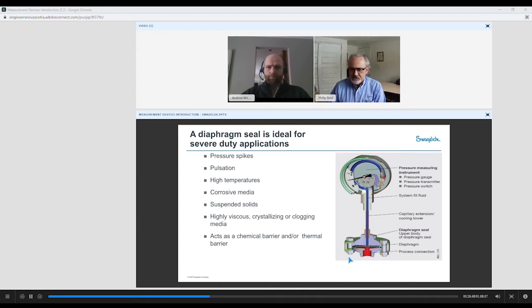So a little bit about diaphragm seals, and we're going to take a break for some questions here in just a minute. A diaphragm seal, as I talked about a little bit earlier, has the process connection on the bottom. It has a diaphragm separating the fill media, and this is a very specific amount of media that's put in and then welded closed. The capillary extension can be extended out in various lengths, and can be used for cooling, or if you need to put the gauge in a remote area from where you're actually taking the measurement. So these can be done in various types of gauges at various lengths.